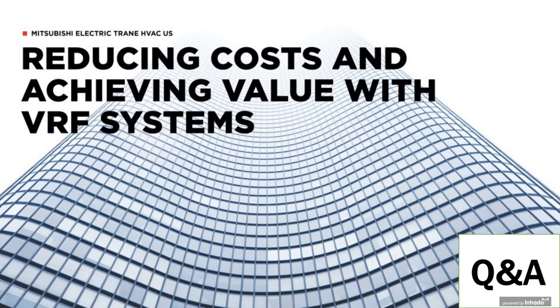Mitsubishi Electric systems are unique in the fact from a heat recovery standpoint, which is a system type that allows you to heat and cool from the same system at the same time. It's a 2-pipe configuration and design. Other manufacturers on the market, for the most part, are 3 pipes. There's an oil recovery pipe that's in there as well, which adds material, it adds labor, it adds cost to the installation and maintenance process. Jose, would you say that's the biggest difference in your mind as you think about the various competitive brands on the market?